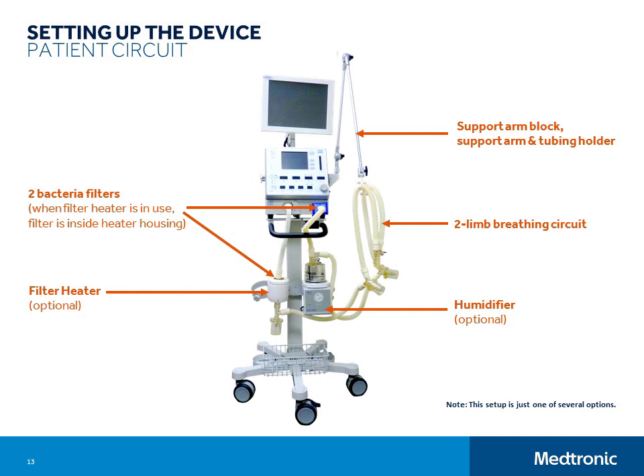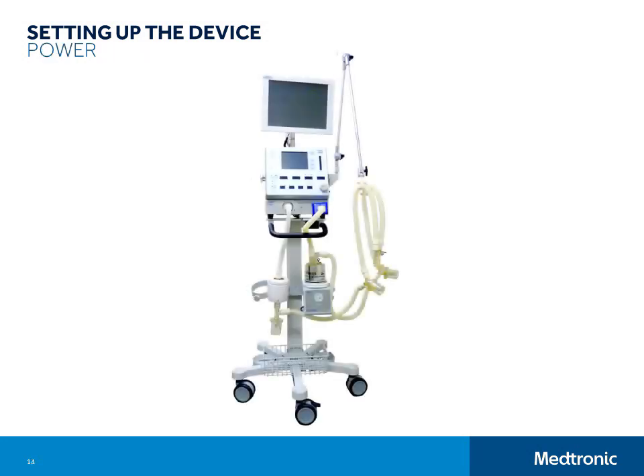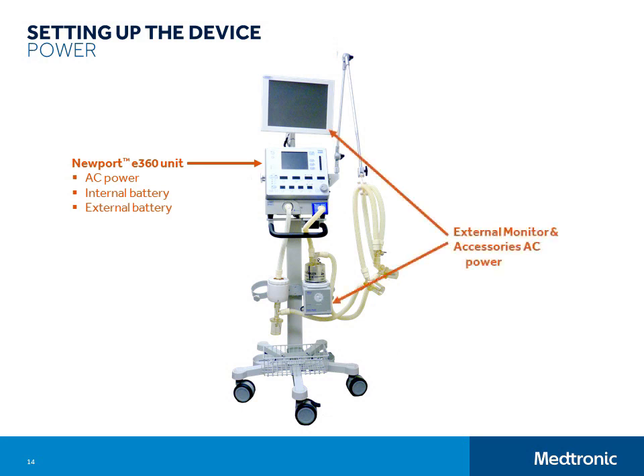Next, we'll connect the E360 and accessories to power. The E360 can run from AC power, internal battery power, or external battery power. The flat panel display, external touchscreen, and other accessories run from AC power. Under normal use, you will plug the ventilator and accessories into AC power. AC power charges the E360's internal battery whenever E360 is plugged in and the indicator on the front panel is lit. If you have an AC power outage or need to move a patient around within the hospital, you can rely on the internal battery to run the ventilator for up to 1 hour.